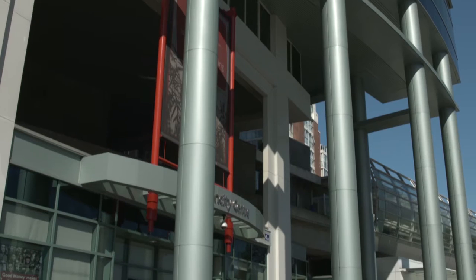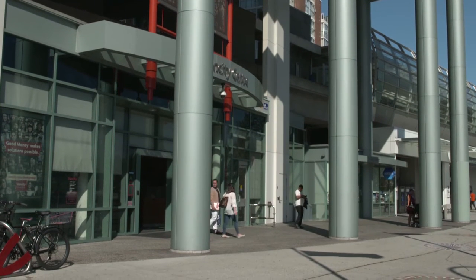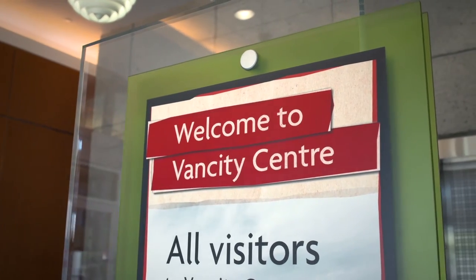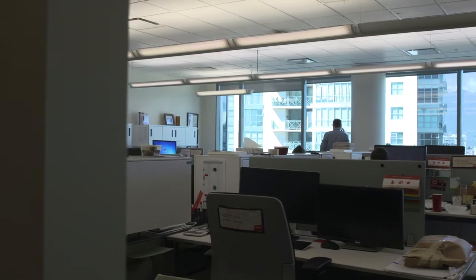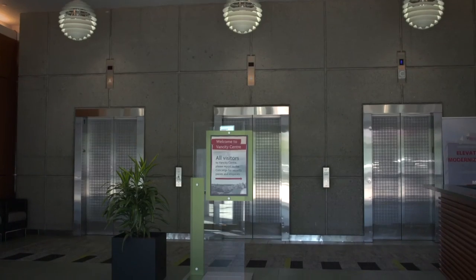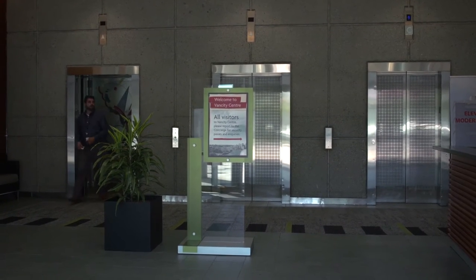So the data center operates today as it did before we started the project, and that's kind of the beauty of this project, is that we didn't really change anything inside the building itself. It still operates the way it did before. All we've done now is we've taken that heat that was previously going through the cooling tower, we've redirected that into the new heat recovery chiller, we boost the temperature of that low-grade heat, put it back into the building. That allows us to significantly reduce the load on the boilers, which is how we've managed to achieve the massive GHG savings for this building.